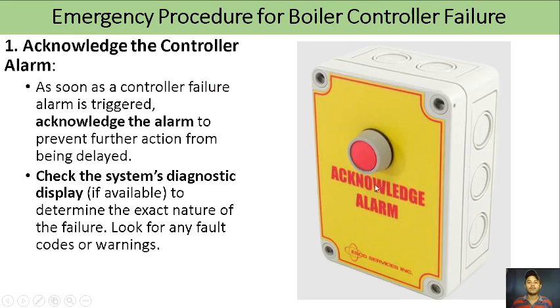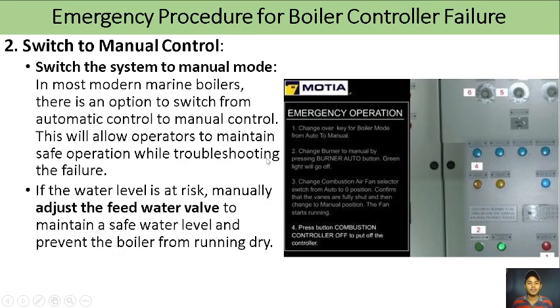So first, if you have a controller failure, acknowledge the controller alarm. As soon as the control failure alarm is triggered, acknowledge the alarm to prevent further action from being delayed. Check the system's diagnostic display if available to determine the exact nature of the failure. Look for any fault codes or warnings. Okay, switch the system to manual mode.